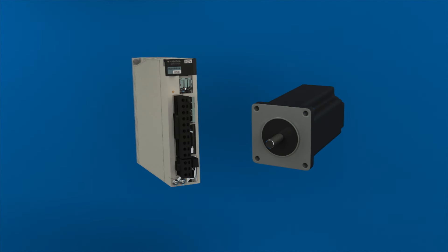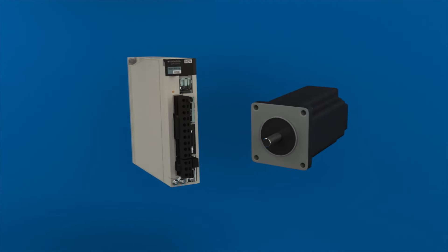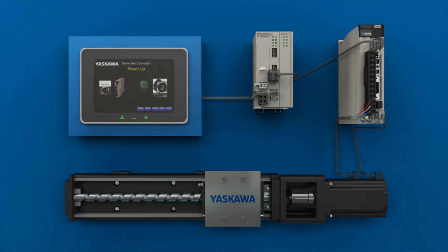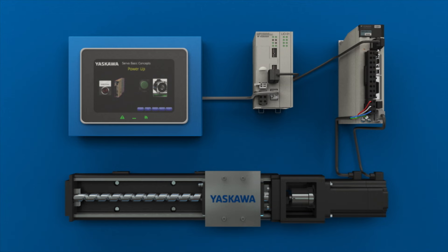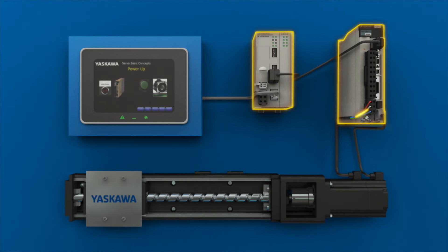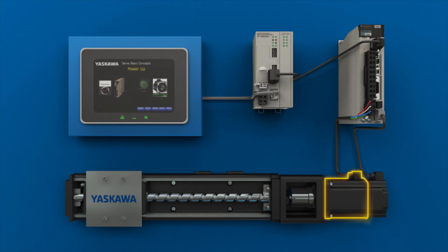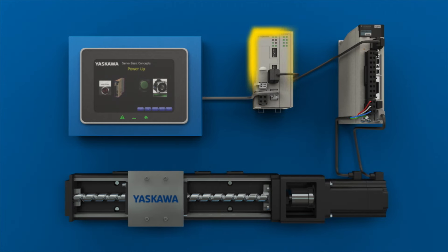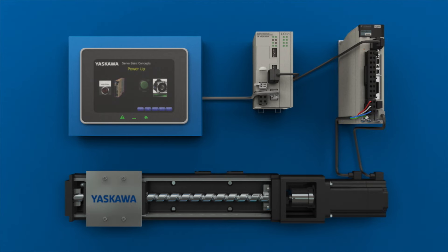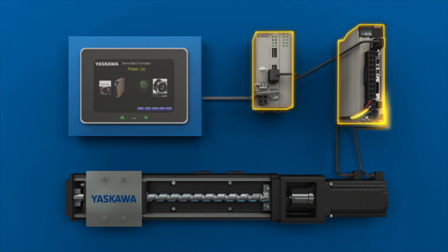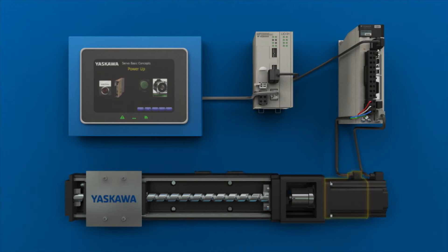Now we have some insight on what a servo is, but we haven't yet described how a servo gets things done. We put a servo to work by making it part of a motion control system. At the input to the servo amplifier is a controller. The controller provides the commands that dictate when and how the servo motor will move. The controller sends commands to the amplifier in the form of an analog signal or data, and the controller and amplifier also exchange position feedback from the encoder.